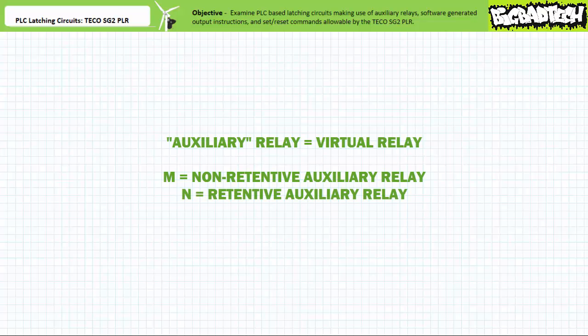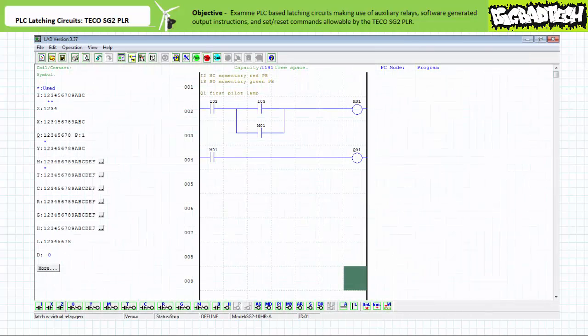Let's first examine holding circuits made possible through the use of virtual relays. The TECO SG2 PLR has two types of virtual relays: non-retentive auxiliary relays that do not maintain the status of the coil and associated instructions at power off, signified by an M, and retentive auxiliary relays that do maintain the status of the coil and associated instructions at power off, signified by an N. Using the TECO SG2 PLR client programming software, we can create a holding circuit using a non-retentive auxiliary relay in the following fashion.